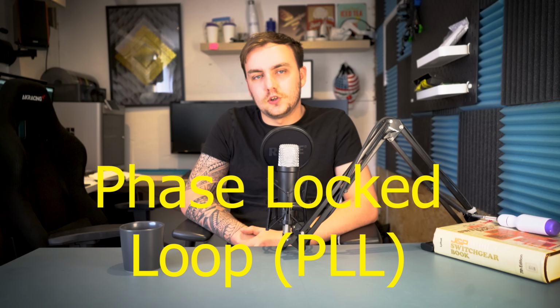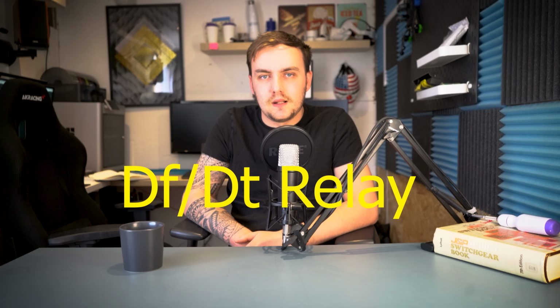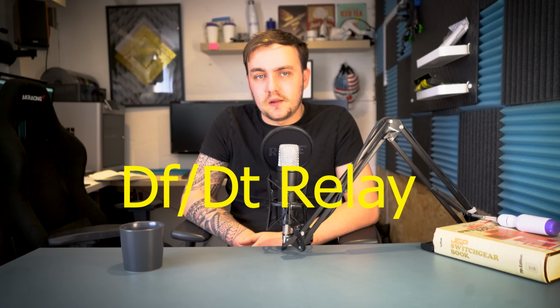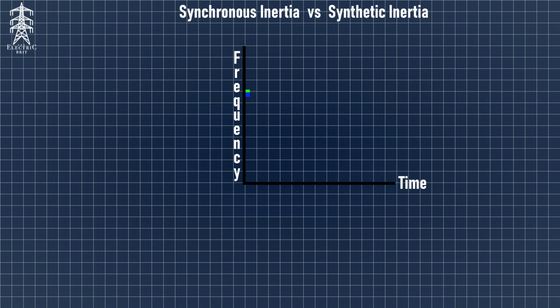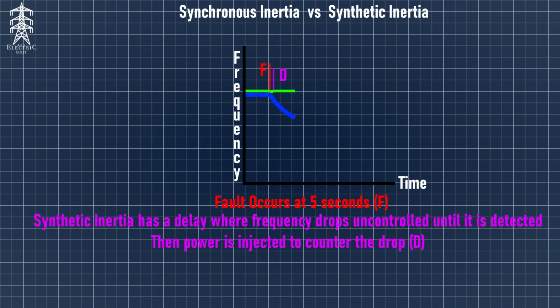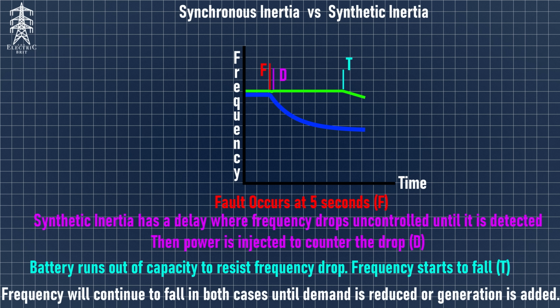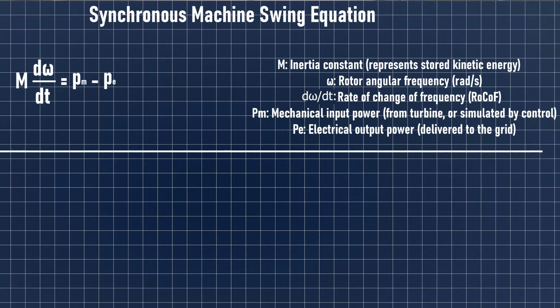The inverters monitor the grid frequency using something called phase locked loops, or PLL for short. A PLL simply generates an output signal with the same phase and frequency as its input signal. This frequency can then inform a relay running RoCoF protection, also known as rate of change of frequency, and in industry is often seen as a df over dt relay. This protection is typically used to disconnect sensitive generators when frequency changes too fast, but can also be used in battery storage systems to inject power into the grid when frequency drops, or absorb power when frequency gets too high, adding stability. The power it puts in or takes out of the system is determined by the synchronous generator swing equation, which emulates a real synchronous generator's inertia.